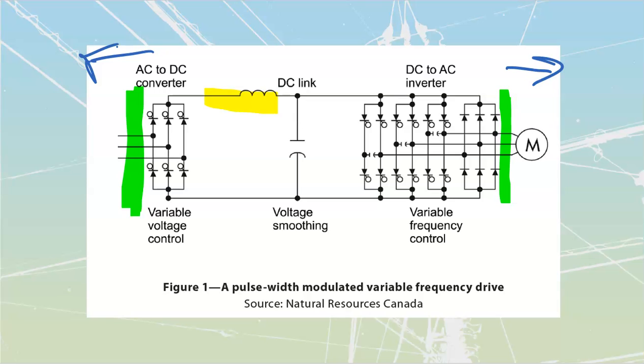We'll use a bunch of different things to do this. Line reactors, isolation transformers, and harmonic filters are going to be common ones. Harmonic filters are just series RLC circuits tuned to specific frequencies so they've got the minimum amount of resistance at those specific frequencies. My other ones, reactors, are just for smoothing. My transformers, isolation transformers, are great because they're basically two reactors back to back that give us double the amount of smoothing.